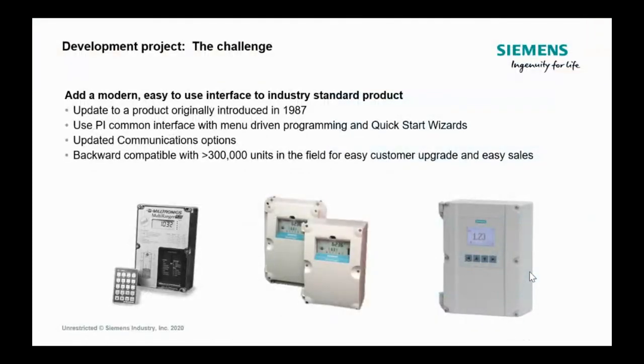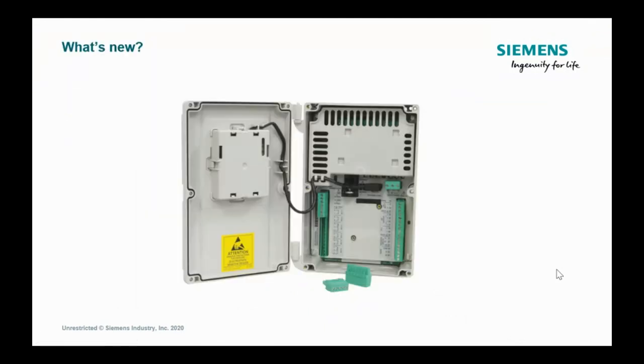As I mentioned, the Hydroranger has gone through a lot of changes. They've been around for a little over 30 years, and you can see the old Hydroranger Pluses. There's still a gazillion of those out there, still kicking. Then we went to the Hydroranger, and now to the Hydroranger HMI. The HMI is the latest and greatest one. As you look under the hood, really it's the same Hydroranger you know and love. They did make it finger safe, and the thing I like is the terminal blocks are removable. If you have big fat fingers like mine and you've ever tried to terminate a transducer in terminals 3, 4, and 5, it can get a little tricky. You can pull the terminal block out, terminate it out in the air, and then snap it back in.